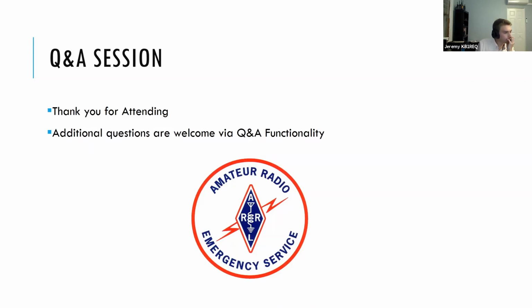All right, and then going back to our discussion that you had on generators and transfer switches. The question here: if you have a manual transfer switch, how do you monitor when the main power comes back on? And how do you handle that switch? Some of them may have an indicator on them, but it's really manual. So it's, you know, when the power company knocks on your door and says, hey, power's back on, or you see your neighbor's lights come up. Again, specific to that component, it may have an indicator of some sort, but it is going to rely on you to go over and actually switch it, both on and off. So there's not necessarily a built-in way to know just looking at a manual transfer panel.